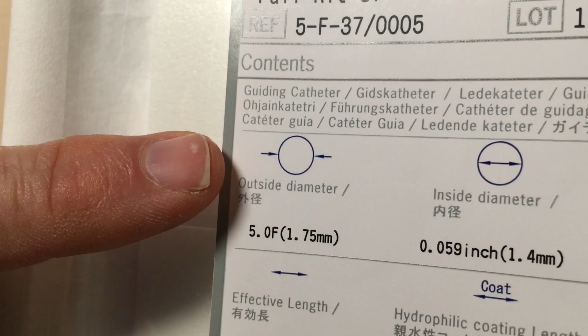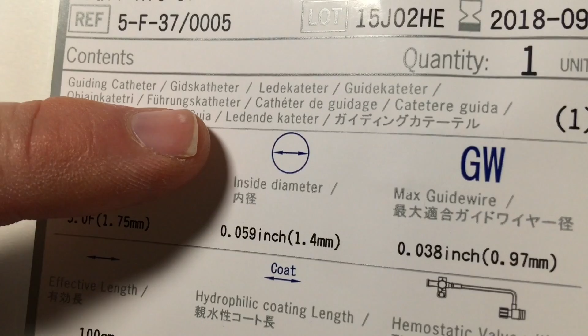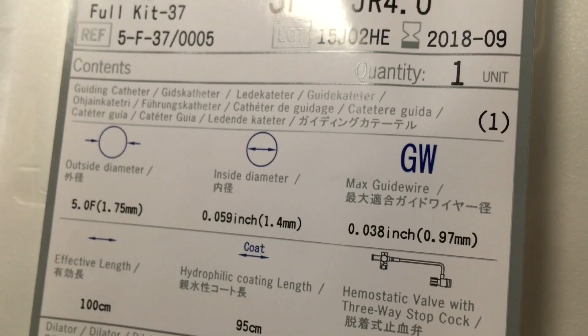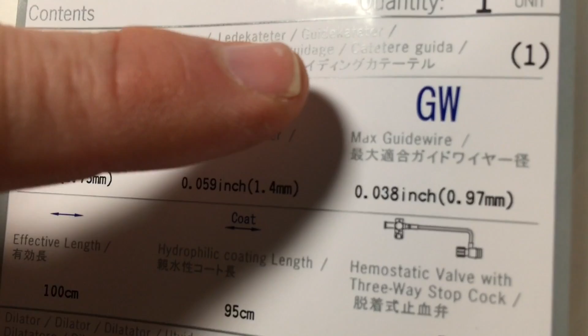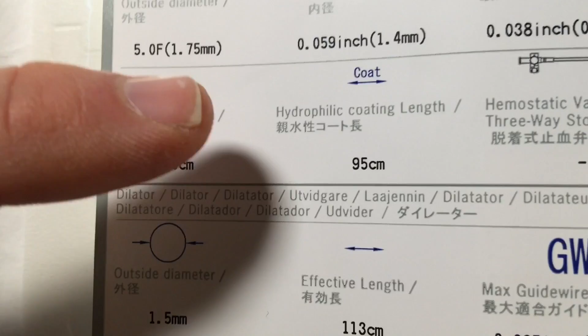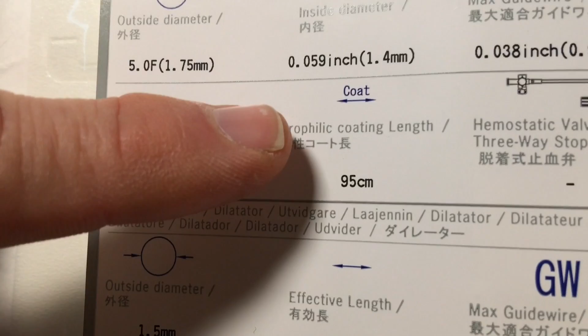The guiding catheter is a 5 French, and its internal diameter is 0.059 inches. The guiding catheter is compatible with a 0.038 inch guide wire. The length of the guiding catheter is 100 cm and it is hydrophilic coated for most of its length, 95 cm.